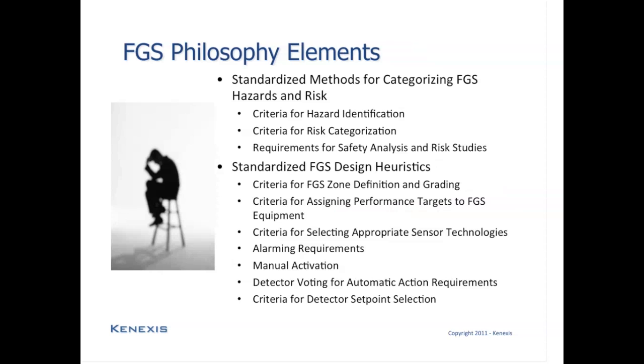Now, the development of a fire and gas system philosophy is going to include multiple elements. First off, the fire and gas system philosophy is going to standardize the methods that are going to be used for categorizing the hazards that fire and gas systems protect against and the risk associated with those systems. First, there's going to be criteria for hazard identification. So for instance, for process facility areas or process facility equipment, there will be rules established to determine whether or not a zone or a piece of equipment has any hazards associated with it.